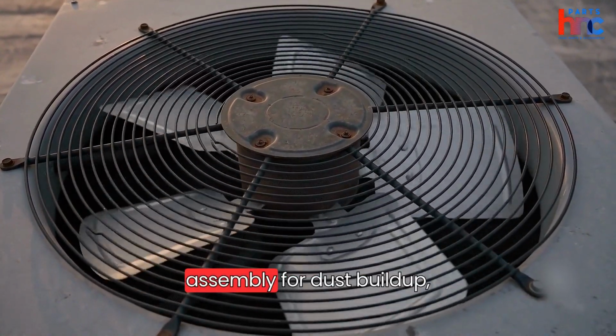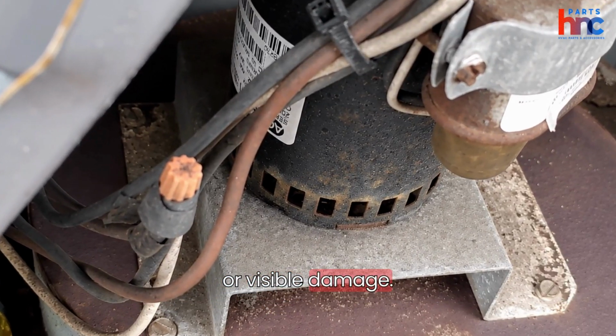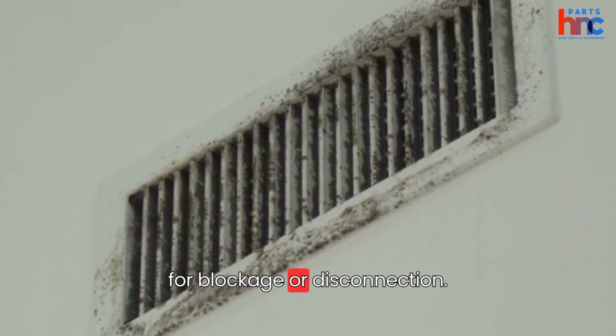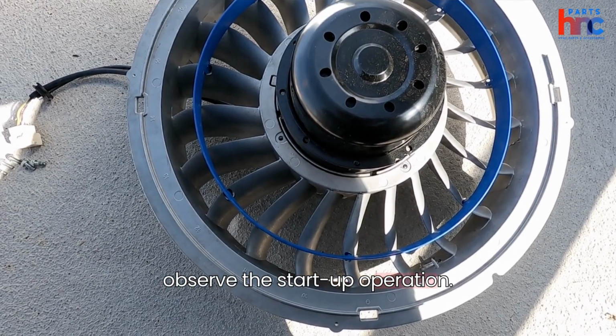First, inspect the inducer assembly for dust buildup, debris, or visible damage. Check vent connections for blockage or disconnection. Next, observe the startup operation.